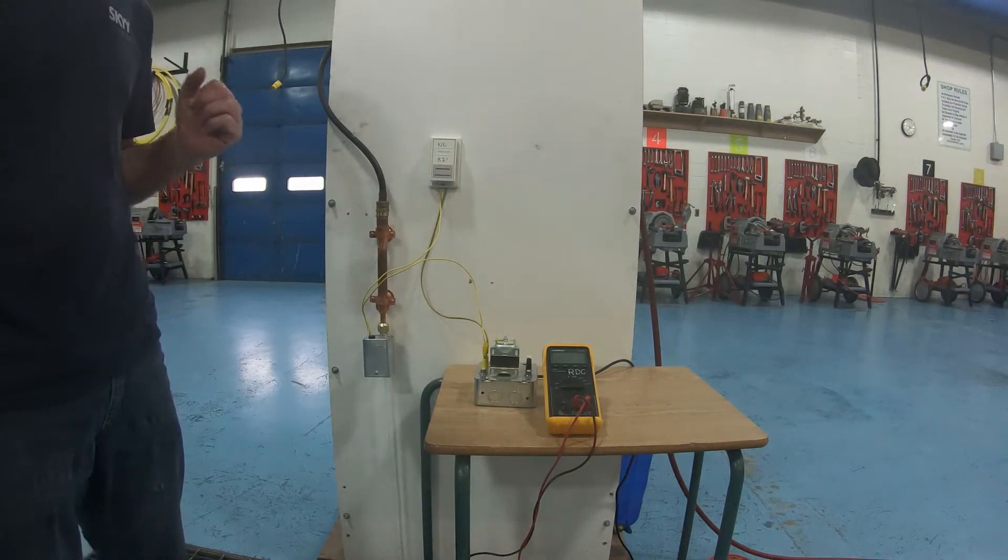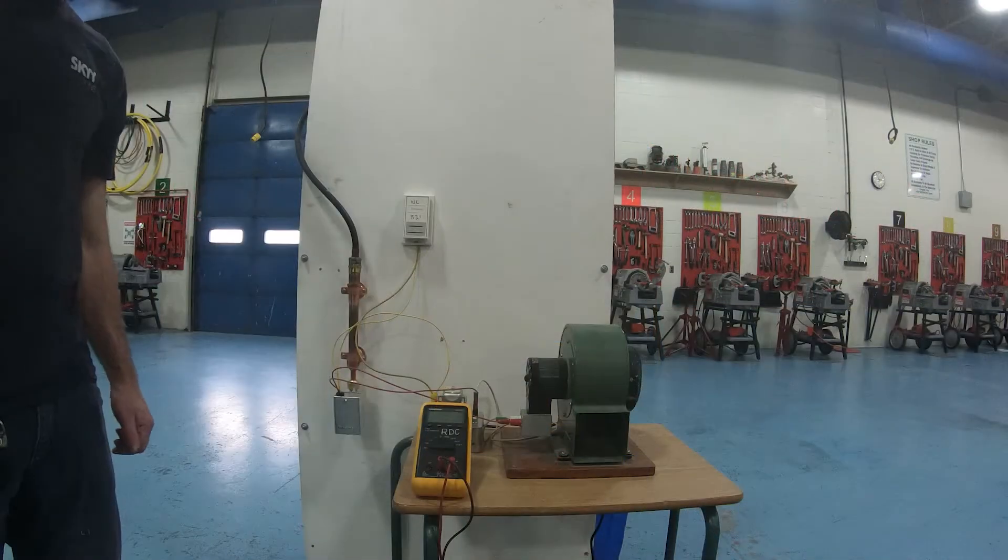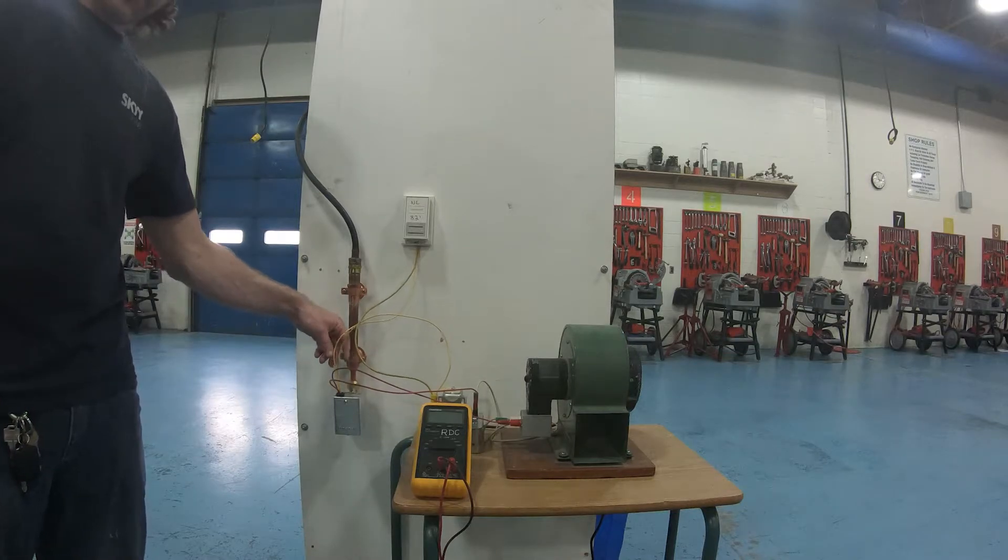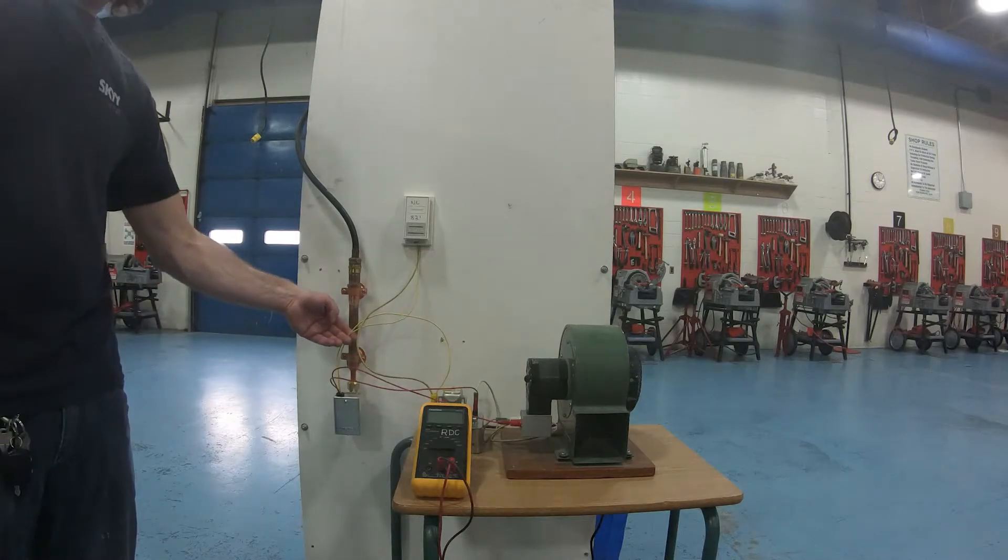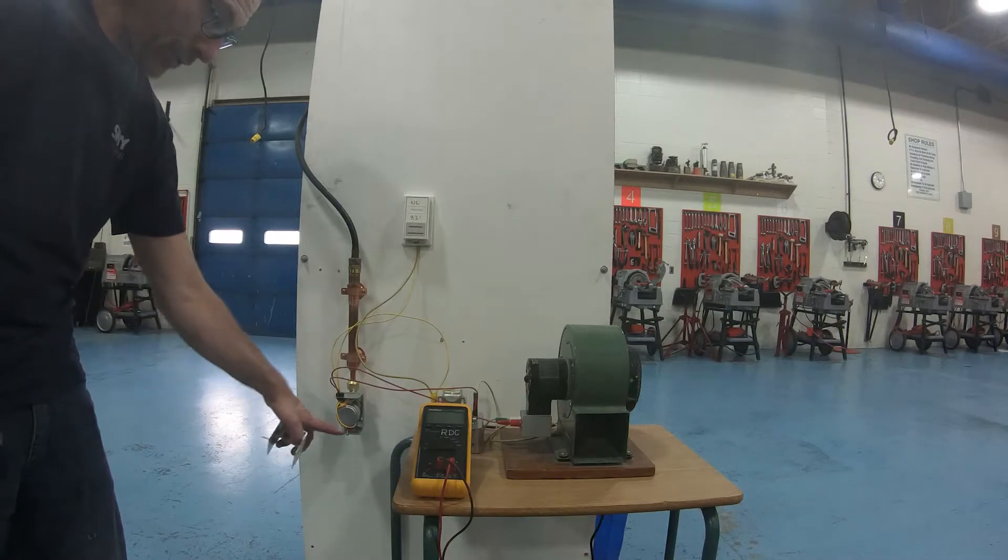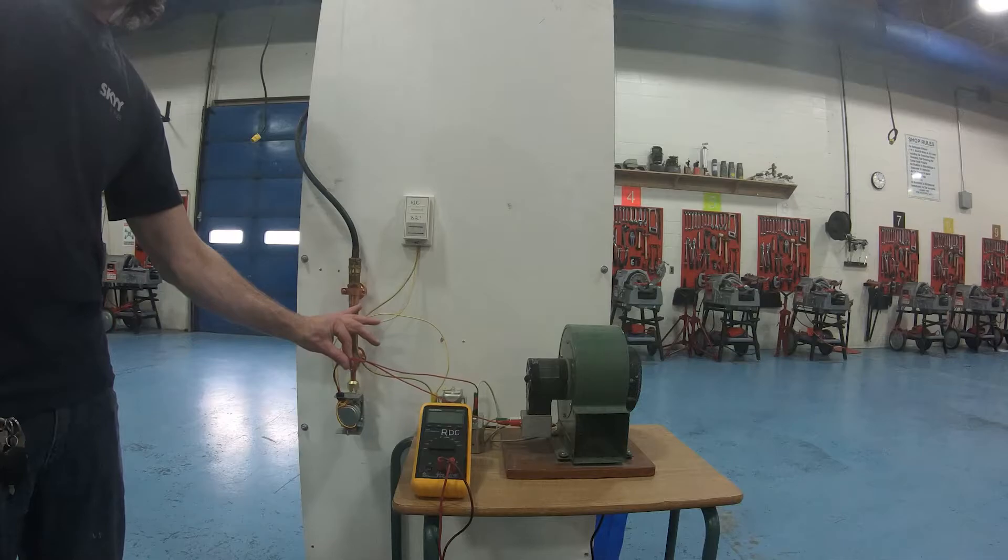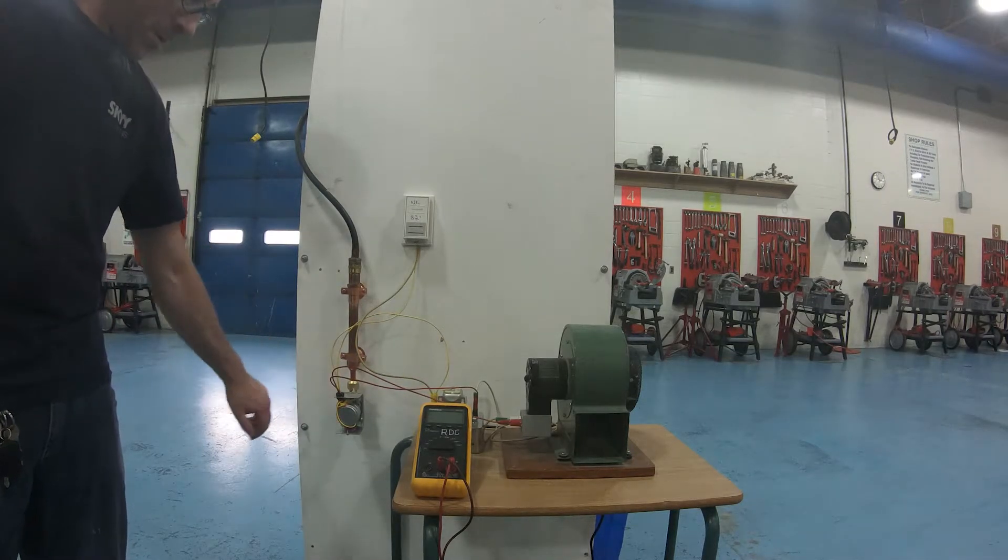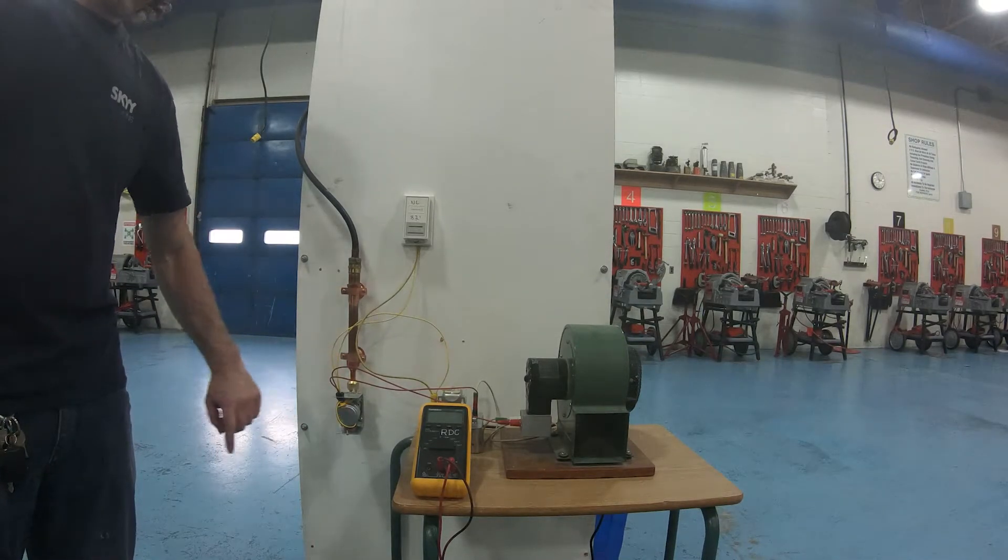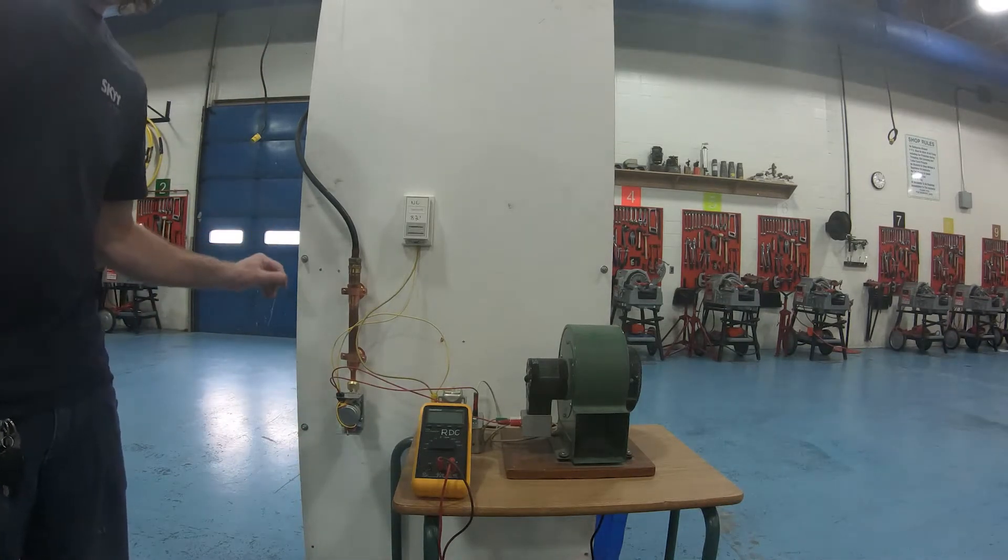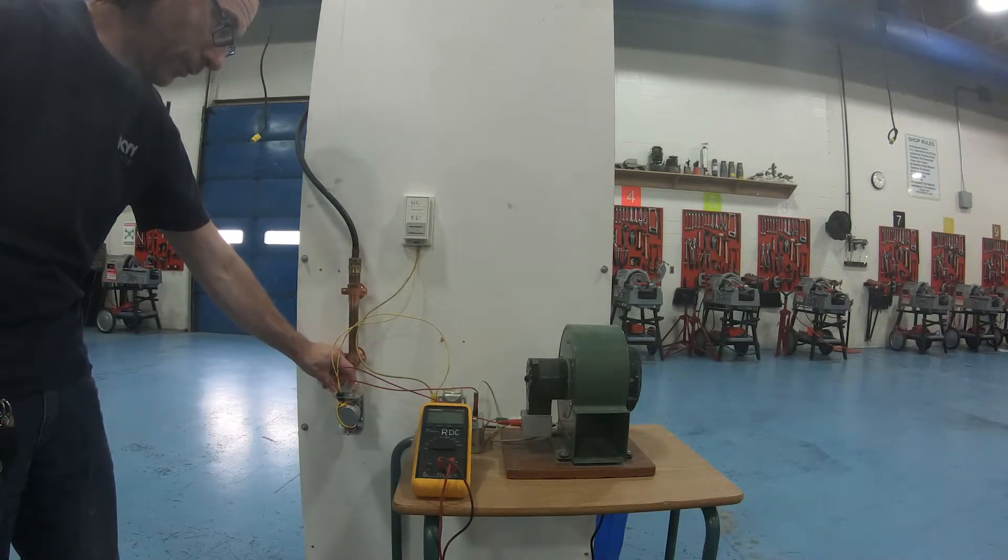So we have our normally closed zone valve with end switch, and I can tell that on the Honeywell zone valve because I have four wires coming out of it. The two yellow ones are for the actual actuator motor, which is this motor right here, and the two red ones are for the end switch, which you can't really see but it's down here. Right now we are powered down. There is no power going to my zone valve motor and I can tell that because no water is flowing out the bottom of my zone valve. I can manually bypass it with a normally closed application with this little lever.